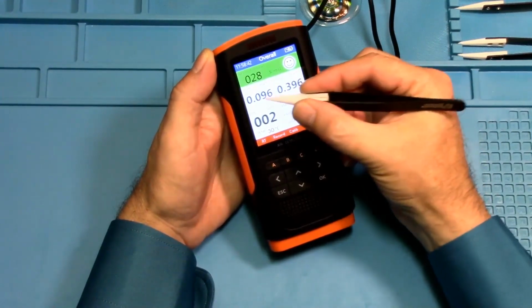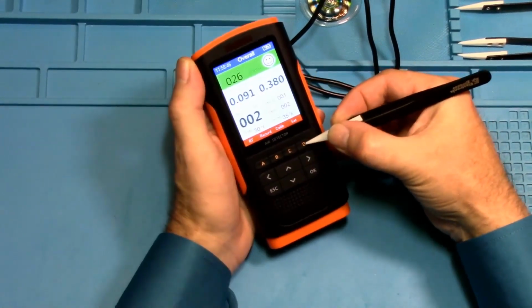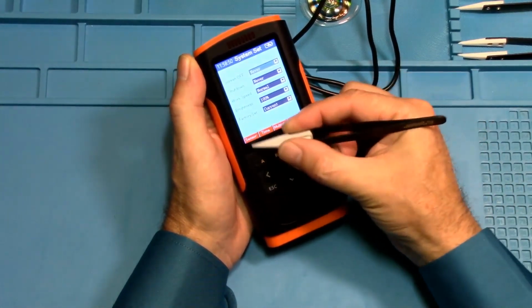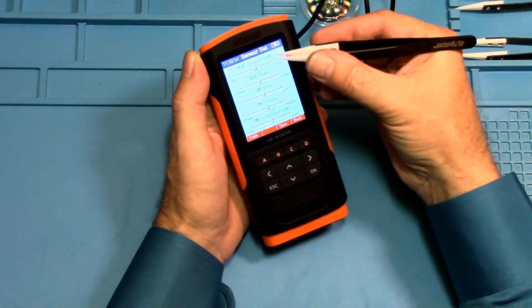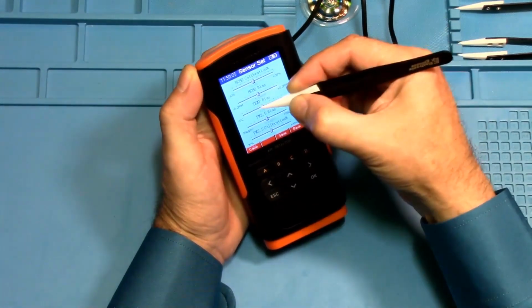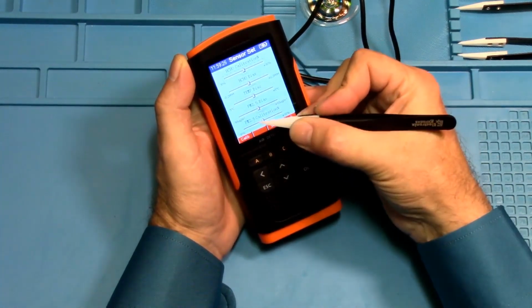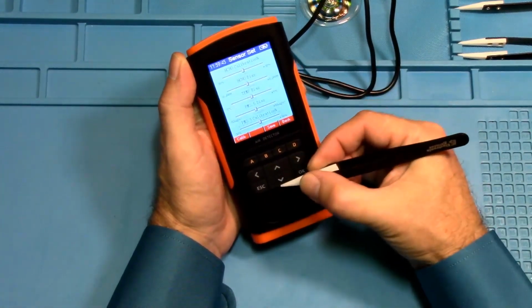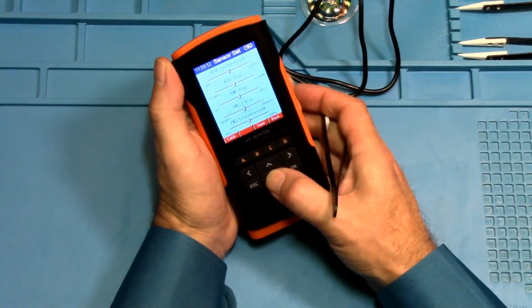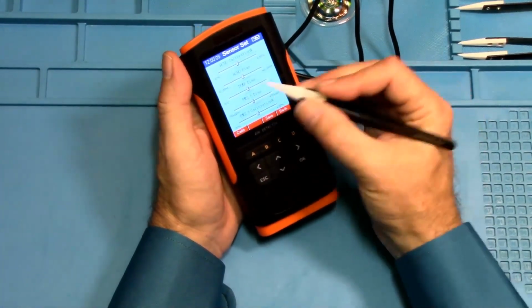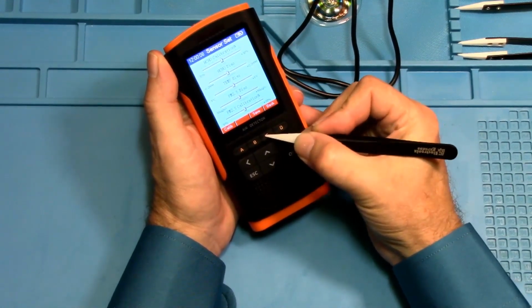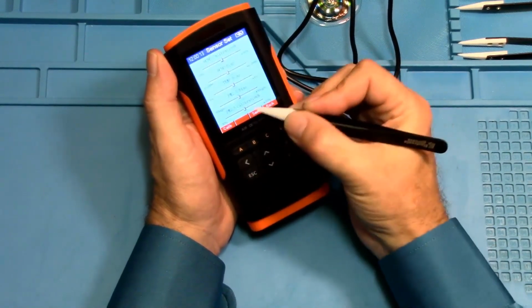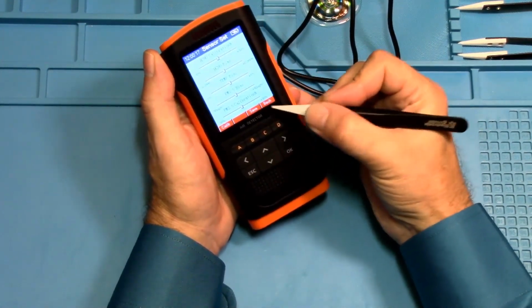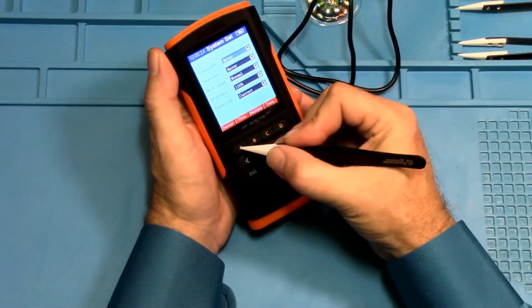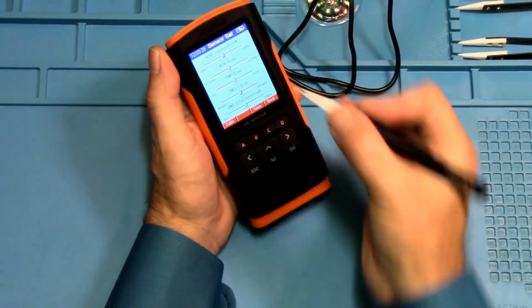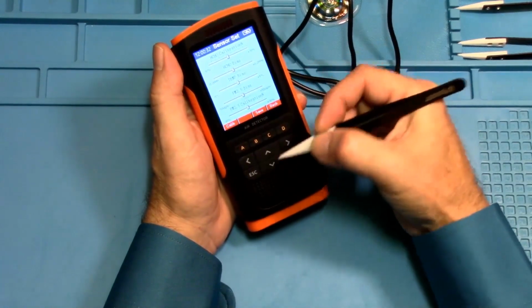Okay, if you want to adjust the calibration of the numbers, go D for set, and then A for sensor, and that brings up your sensors that you can change. Formaldehyde bias, temperature bias, particle matter 2.5 bias, and then the calibration. So that's it. Nothing about TVOC. Evidently you can't change TVOC. And then once you've made your changes, the C button will be for the save. That's how you save your setting. And if you get into here and just decide not to do anything at all, then the D button will be for back, to go backwards.